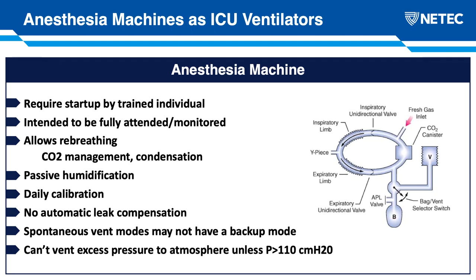So we need to make sure as we're setting these up that we are going through the process of checking the alarm limits, but also making sure we're turning up the volume, because the default volume of alarms is not nearly what we're used to from our ICU ventilators. We talked a little bit about rebreathing and the implications of rebreathing, namely that we have to manage the CO2 of exhaled gases if rebreathing is occurring.